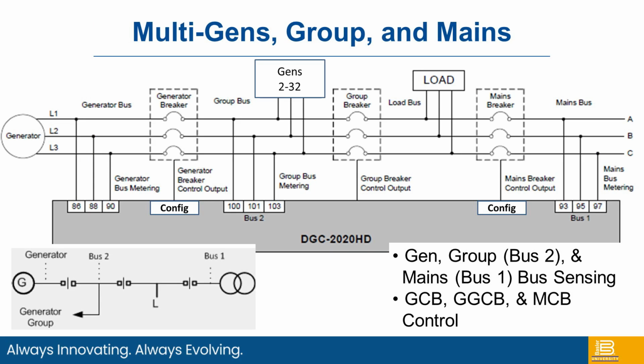We also have the capability of doing multiple gens, the group breaker and the mains breaker. As I had stated earlier, one of the highlights for the DGC-2020HD is that we're one of the only few in this industry that can actually control 3 separate circuit breakers, and we have full sensing, both voltage and current, for all of those. As you can see, I put in here configurable for these breakers, so we can configure the HD to be able to control any breaker that's out there.